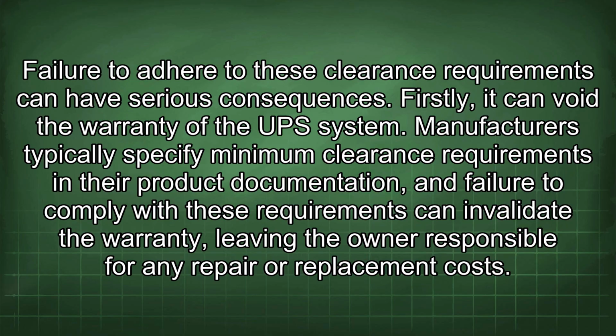Failure to adhere to these clearance requirements can have serious consequences. Firstly, it can void the warranty of the UPS system. Manufacturers typically specify minimum clearance requirements in their product documentation, and failure to comply with these requirements can invalidate the warranty, leaving the owner responsible for any repair or replacement costs.